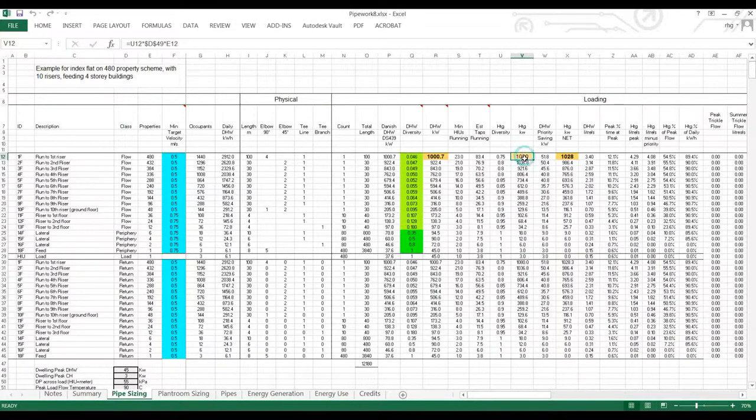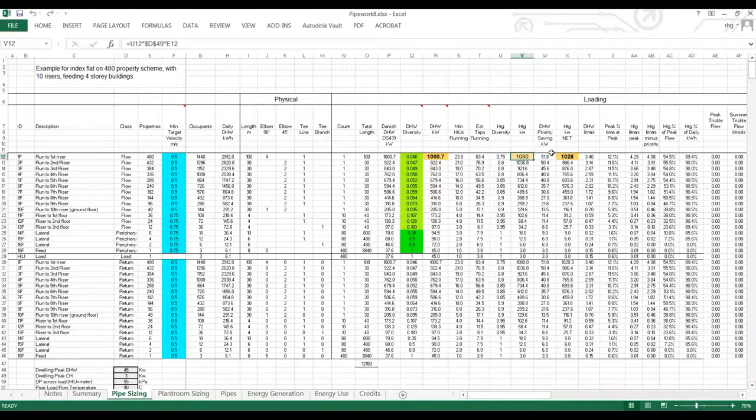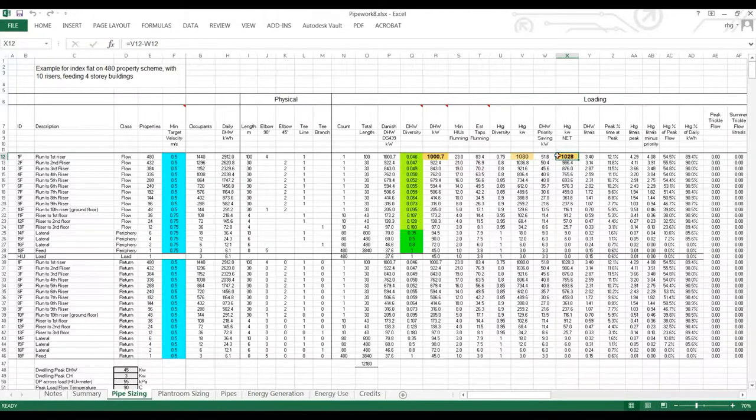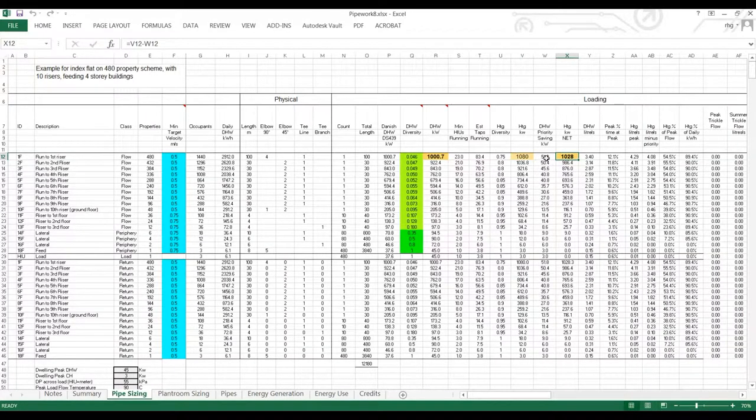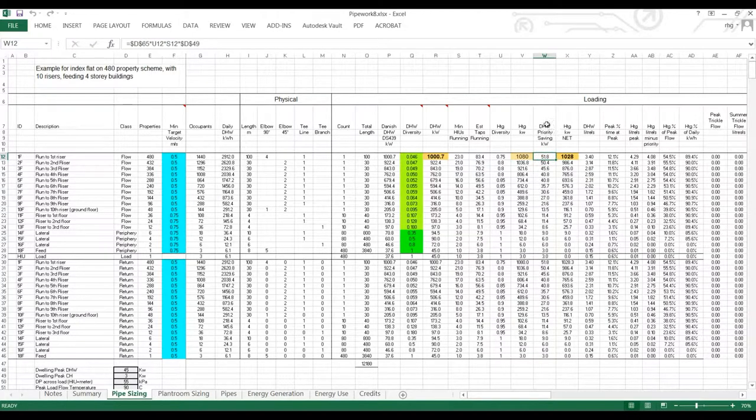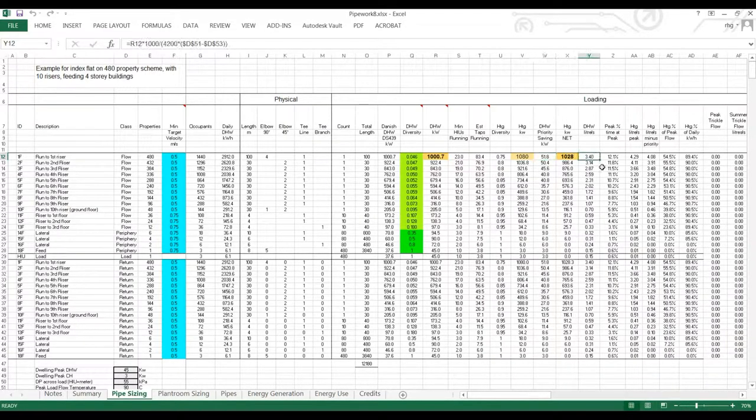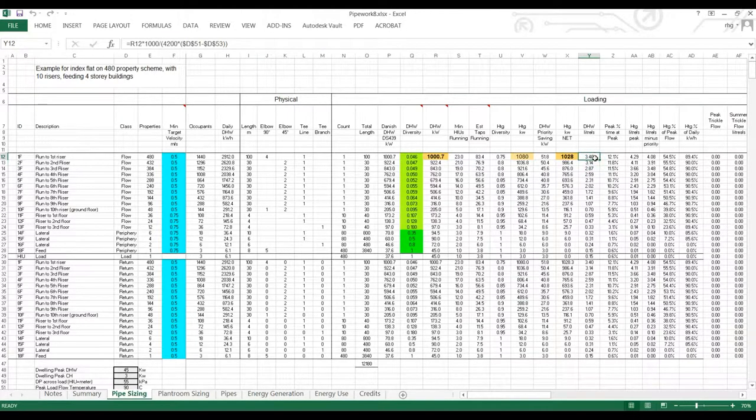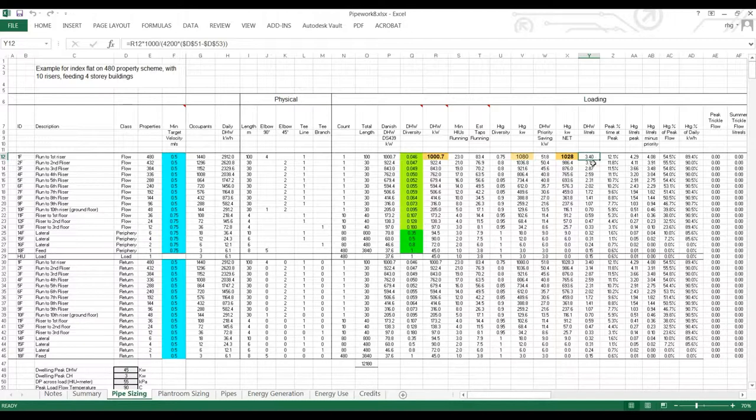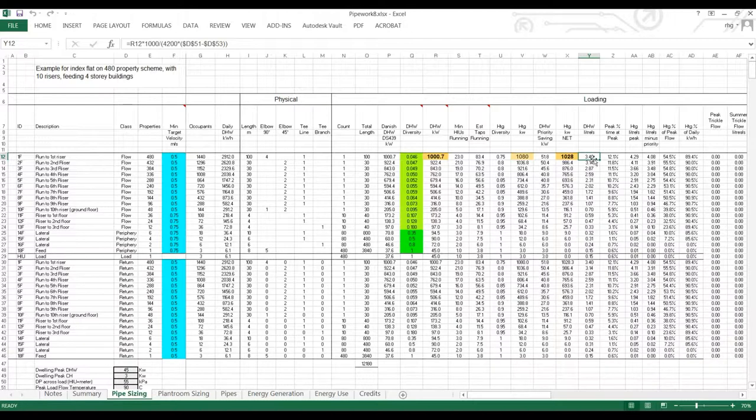This gives us a calculated heating output, which in turn gives us the total diversified load. We also bring into account the savings from hot water priority, which come from the minimum number of HIUs running. We have the calculated peak flow. So this is the peak load for domestic hot water divided by the temperature drop, the flow temperature minus the return temperature from the HIU in hot water mode.